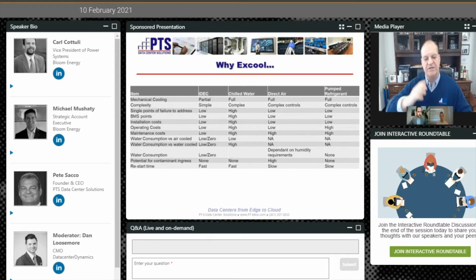Again, it's sized depending on the environment and place in the world where we put this. But it has low single points of failure and BMS points. It greatly reduces the complexity of operating to a single box. So my installation cost is down, my operating cost is low, my maintenance cost is low. You can use little to no water, again depending on where you are. Its restart time is really fast, and you have no potential for contaminant ingress into the data center floor.